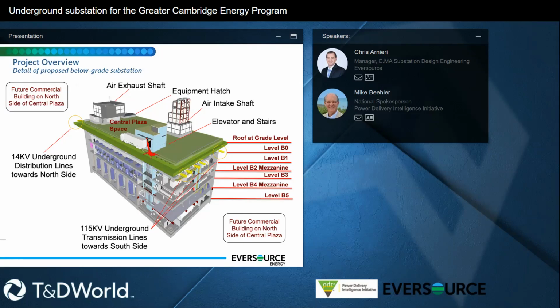Overview here is we can see where the distribution duct banks, which we already talked about, the transmission, but then we can start to get a better understanding of the 7 floors that Mike mentioned before, where we have the B0 level, B1. The mezzanine levels are functionally cable routing levels or gas insulated bus routing levels to get from one side of the station to the other and do that cleanly and accurately. And then finally our B5 level, which has all the heaviest pieces of equipment.